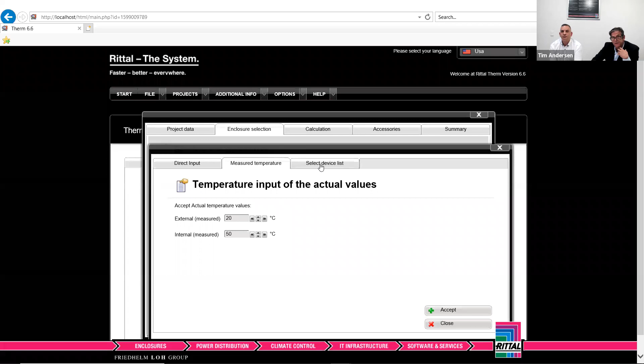So then going a little bit further along, rather than measuring the temperature to determine our heat load inside there, we can actually go through Rittal's database. And this is where the phone app doesn't have access to this. You can only do it through direct input. But if you download the full version, it runs straight off, and you can pretty much go in and pick certain devices. Now, because we're talking about technical products, I'm going to start with basic electrical. So I can pick, for example, a circuit breaker, and then determine, based on the size, which is an 80 amp circuit breaker, and that would correspond over here. It says 14 watts of heat, which is almost insignificant, but one enclosure wouldn't have one circuit breaker. So when you start adding things up, you'll be surprised.